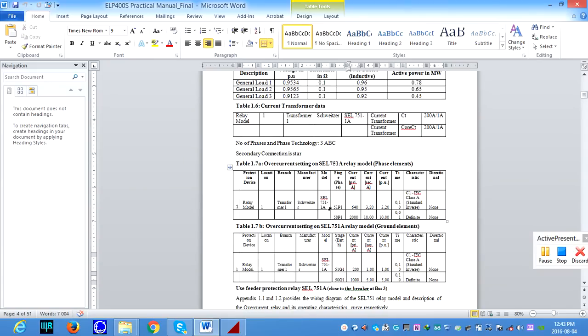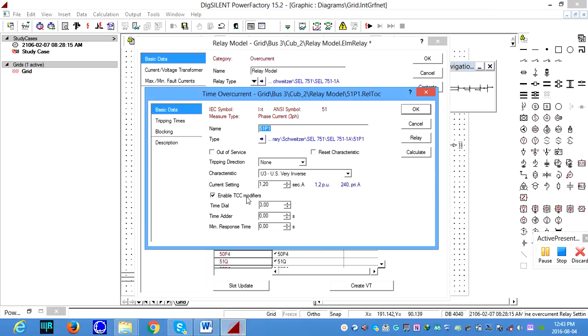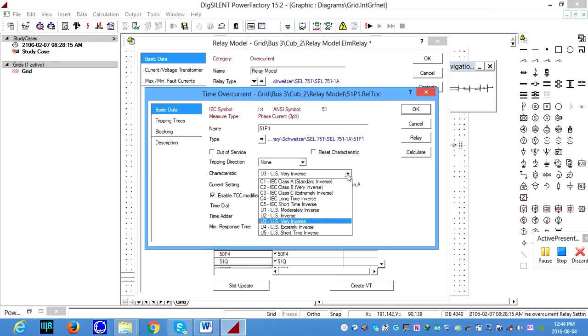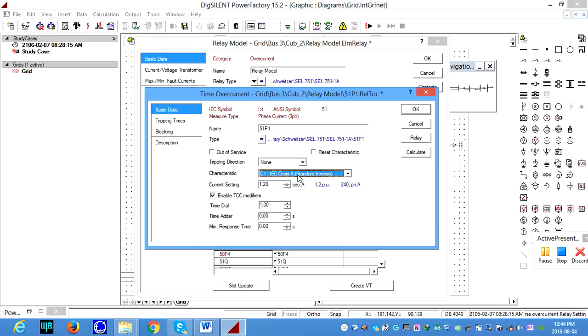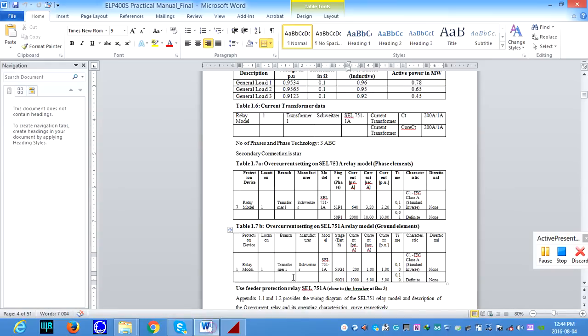Okay, you can see 51P1. We need to make the settings 51P1. So the tripping direction is non-directional. I think you should make it either forward or non-directional, but in this case, the tripping direction we're not considering. And the characteristic, if you look at the manual, is IEC standard inverse. If you look here, IEC class A standard inverse.